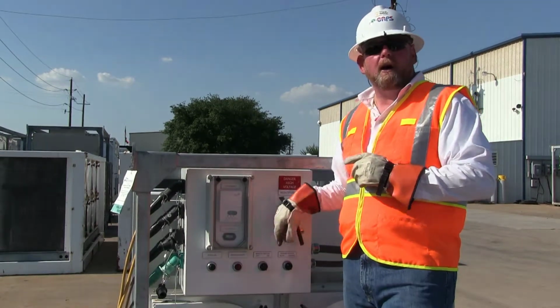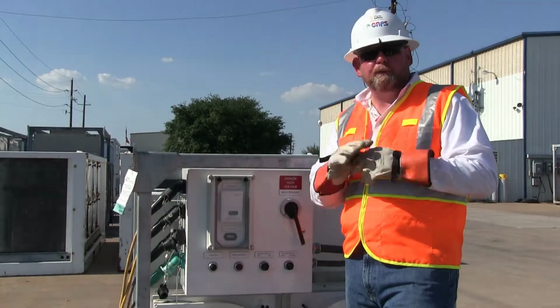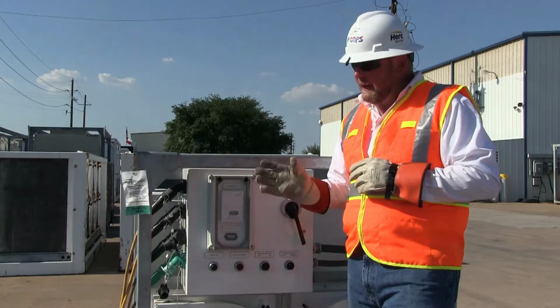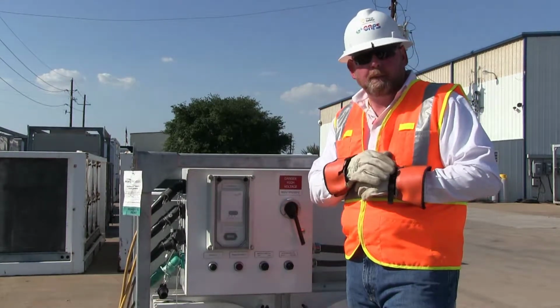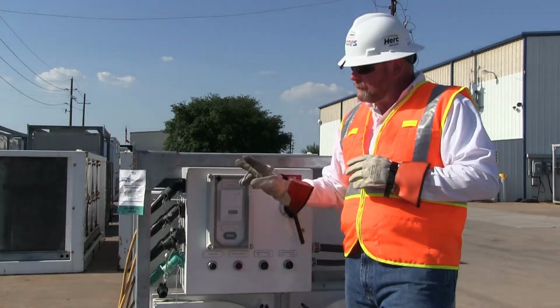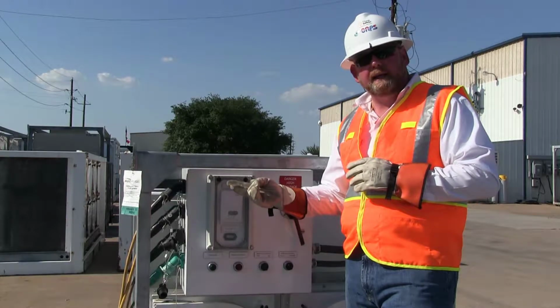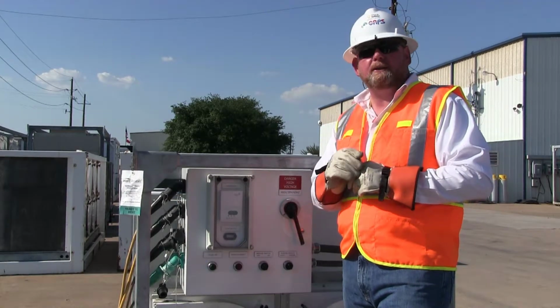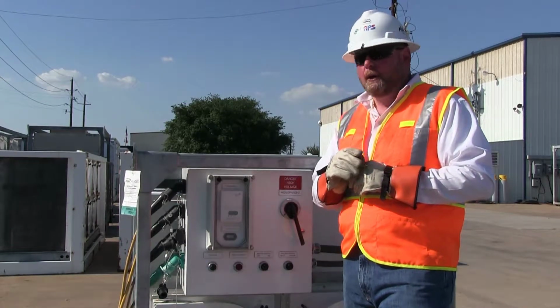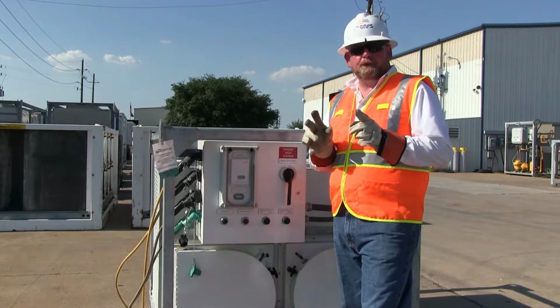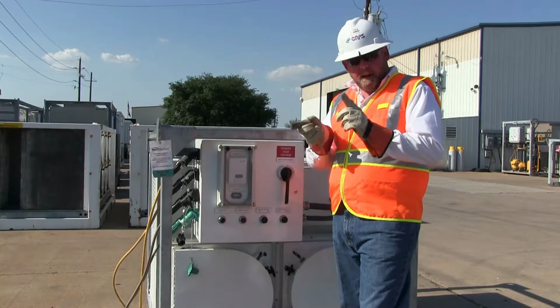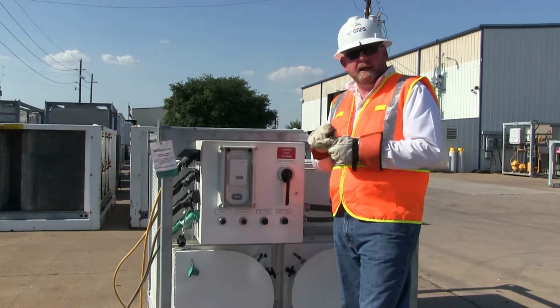Turn our breaker back off. What that indicates is we have 2 phases that are backwards. What we're going to have to do is lock and tag out our primary power, and we're going to have to change 2 of our main incoming leads. Please note, you never change the incoming leads of your cam locks with the main line energized. We've changed 2 leads, our A and B phase, by reversing them with a de-energized cable.